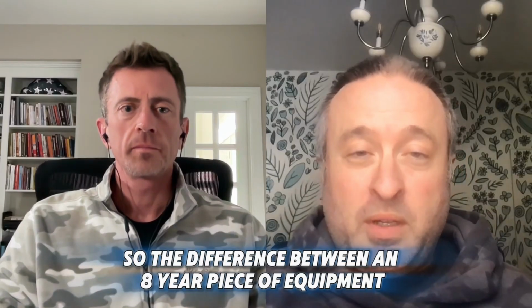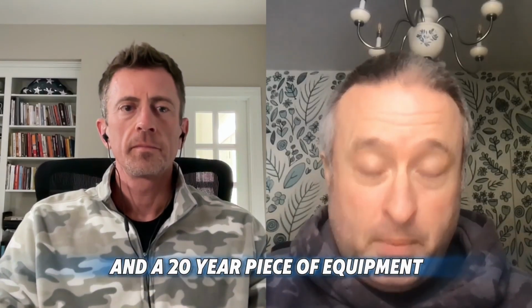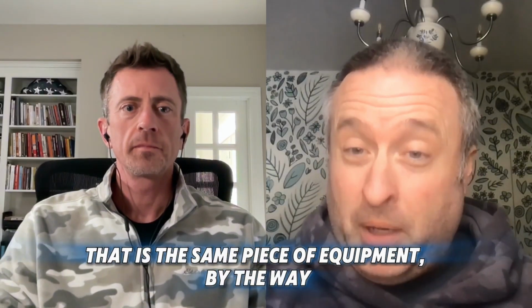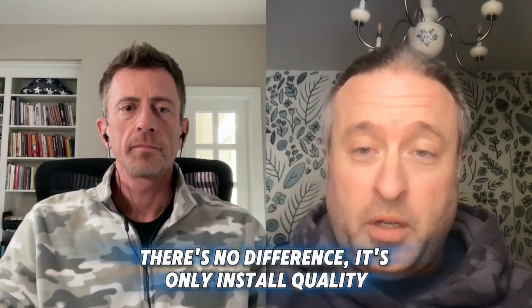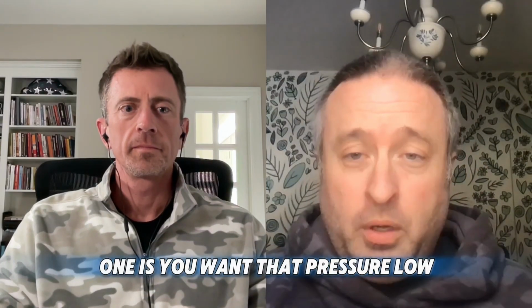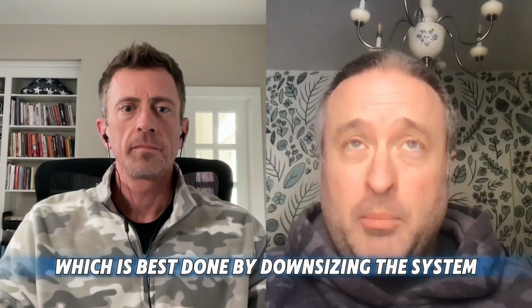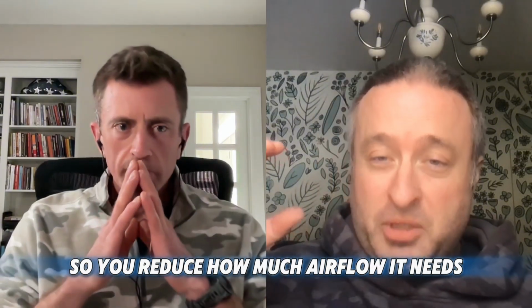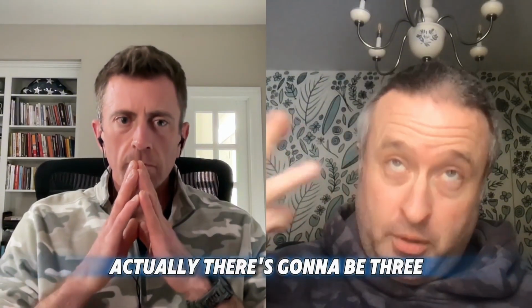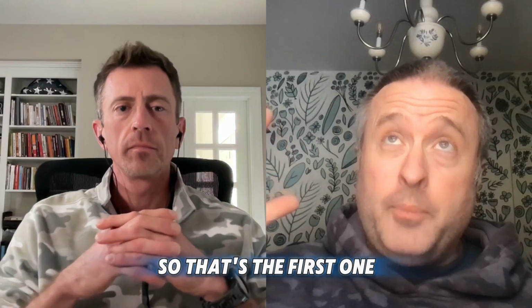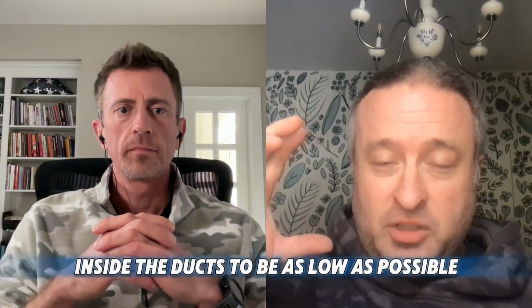So the difference between an 8-year piece of equipment and a 20-year piece of equipment, that is the same piece of equipment, by the way. There's no difference. It's only install quality. One is you want that pressure low, which is best done by downsizing the system so you reduce how much airflow it needs. Actually, there's going to be 3, so that's the first one. You want that pressure inside the ducts to be as low as possible.